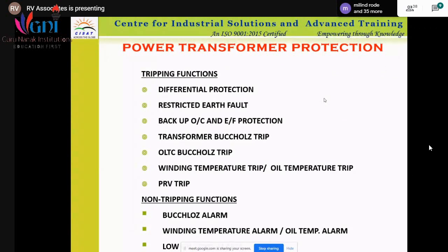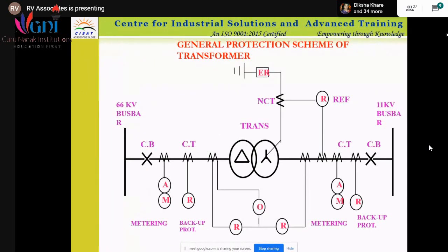These are all the transformer protections which we are using. What we say is monitoring protection. First is the differential protection, which is a tripping function. Then restricted earth fault, also a tripping function. Backup overcurrent and earth fault protection is a tripping function. Transformer Buchholz trip, a tripping function. OLTC Buchholz trip, a tripping function. But similarly, there are some non-tripping functions, what we call the alarms. That alarm is the Buchholz alarm. Then WTI, OTI, winding temperature alarm, oil temperature alarm. Similarly, low oil level is an alarm. So these are all the functions we use. This is the general connection of differential protection of a transformer for monitoring.